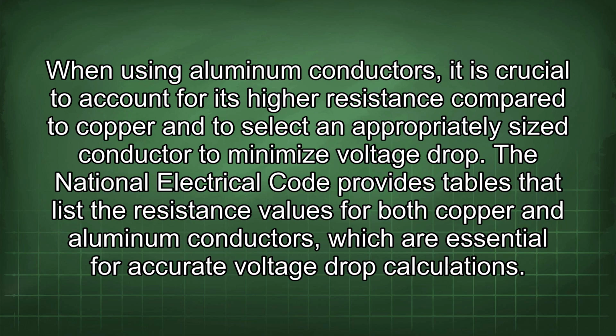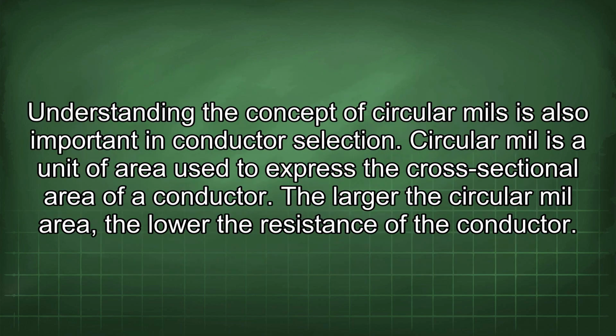The National Electrical Code provides tables that list the resistance values for both copper and aluminum conductors, which are essential for accurate voltage drop calculations. Understanding the concept of circular mils is also important in conductor selection. Circular mil is a unit of area used to express the cross-sectional area of a conductor. The larger the circular mil area, the lower the resistance of a conductor.